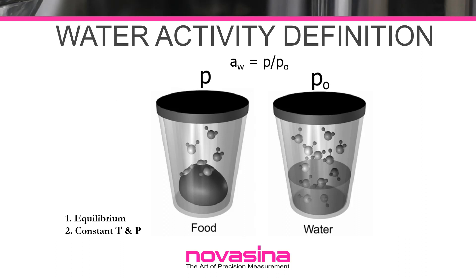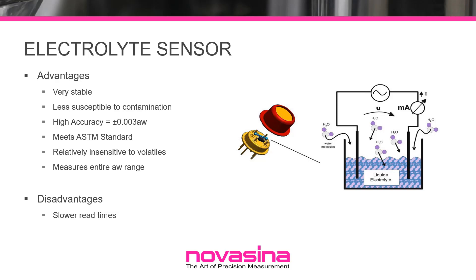Water activity is measured by equilibrating the liquid phase water in the sample with the vapor phase water in the headspace of a closed chamber, and measuring the equilibrium relative humidity in the headspace using a sensor. The relative humidity can be determined using a resistive electrolytic sensor, a chilled mirror sensor, or a capacitive hygroscopic polymer sensor. Instruments from Novasina, like the Lab Master Neo, utilize an electrolytic sensor to determine the equilibrium relative humidity inside a sealed chamber containing the sample.